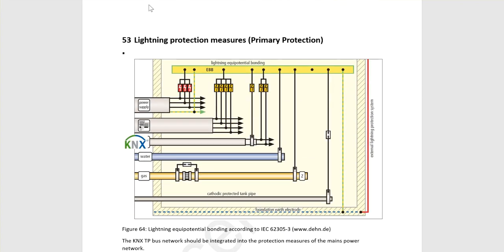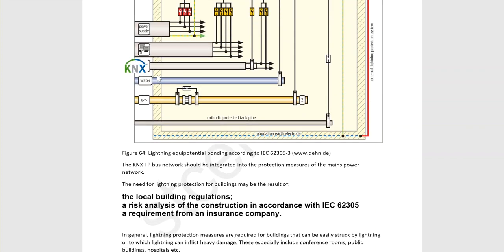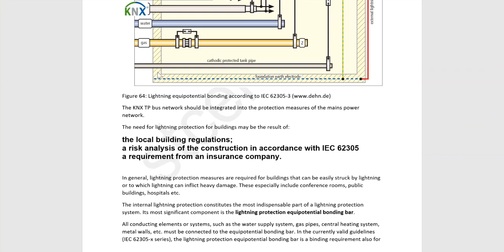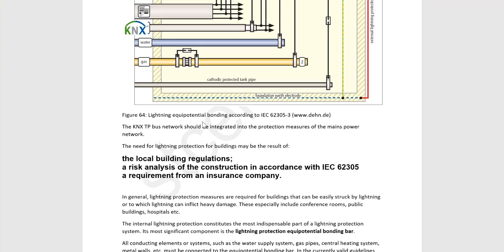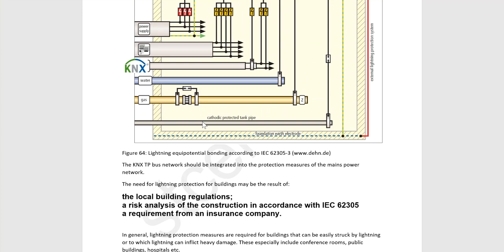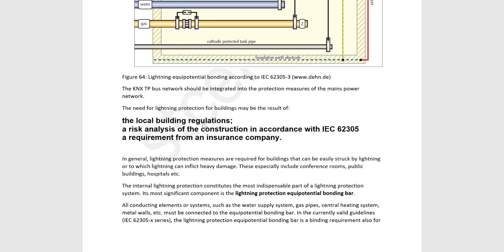Nice. Now here it is going to say about lightning protection measures. The KNX TP bus network should be integrated into the protection measures of the main power network. The need for lightning protection for a building may be the result of the local building regulation. So maybe the local regulation forces you to connect the KNX to the lightning protection, so you should follow something, as I said. A risk analysis of the construction in accordance with IEC, or a requirement from the insurance company. So maybe the local regulation asks, maybe the standard asks, or the insurance company asks.